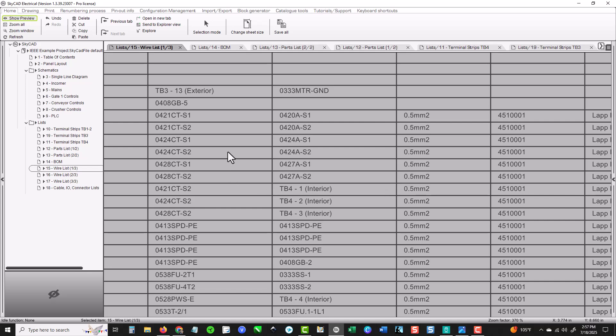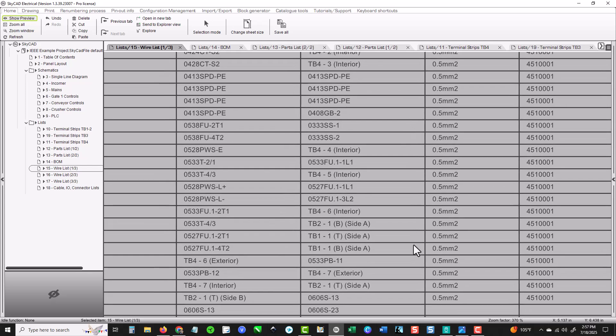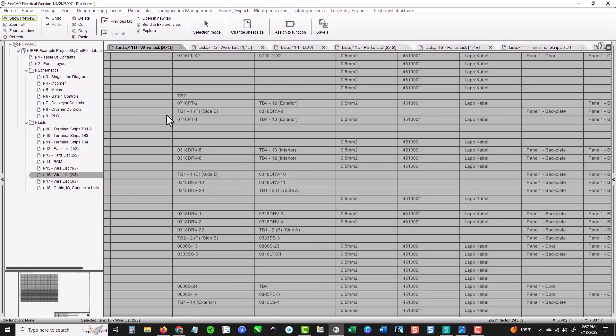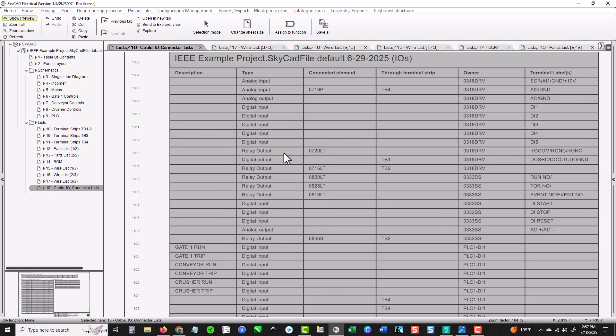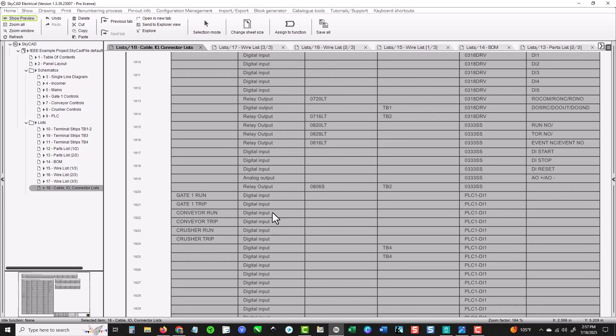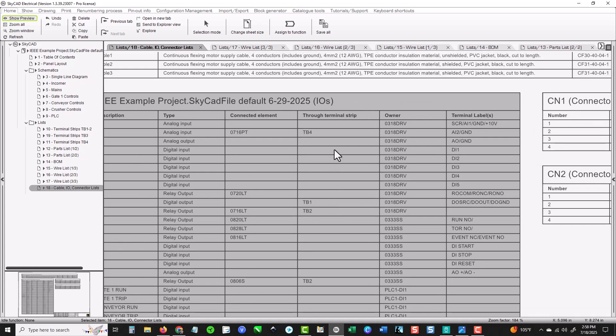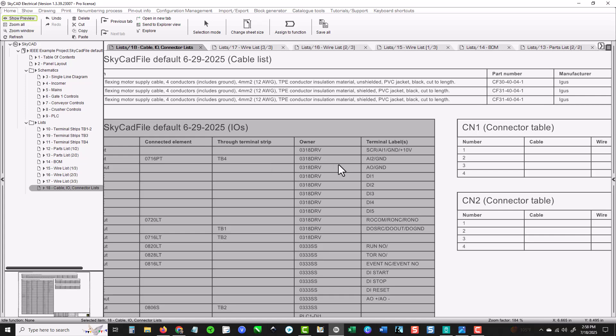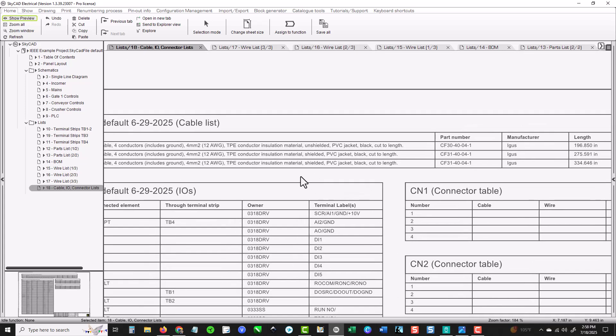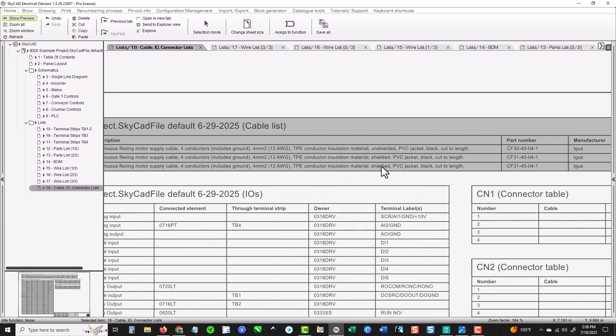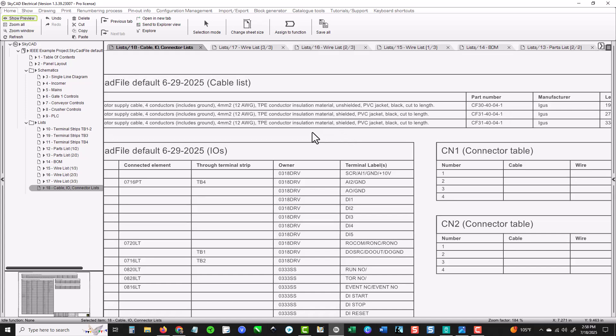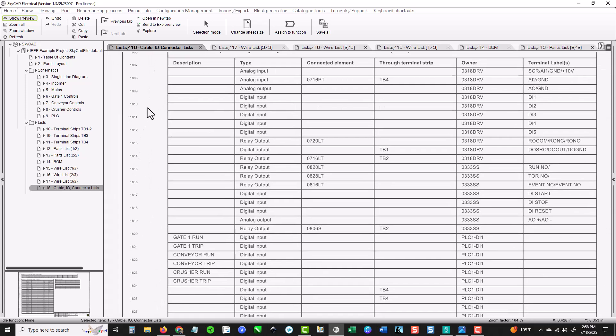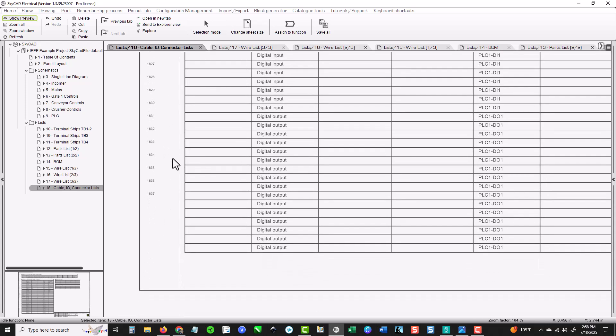A wire list is going to be important — you'll always have a wire list within your drawings. It gives you wire sizes — all in metric here, so Google is your best friend on that. I think these are 16s going through there. It gives you all your locations of your drives and starters, terminal boards, where it lands, side A, side B. Here are your digital inputs and analog — you'll have all of that within your paper pages. There are different types of shielded and unshielded cable. For shielded, you're only supposed to land the ground on one end — generally at the device.